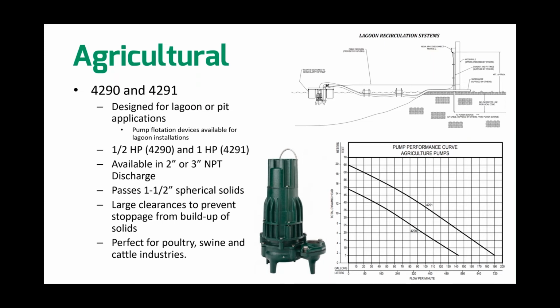The 4290 and the 4291, these are a little bit special. They're designed for lagoon or even pit applications. And as you can see in the top right-hand corner of the screen, you'll see this pump being used in lagoon applications for recirculation. These pumps are half horsepower, which is the 4290, and 1 horsepower, which is the 4291. You can see the performance curve over there at the bottom right-hand corner of the screen. These pumps are available in 2-inch or 3-inch NPT discharge. The spherical solids passing for these pumps is 1.5 inch. The large clearances to prevent stoppage from buildup in solids is great on these pumps. The applications for these, you can use them in poultry, swine, cattle industries, anything when it comes to the farming and agricultural side of things. This is a perfect pump.